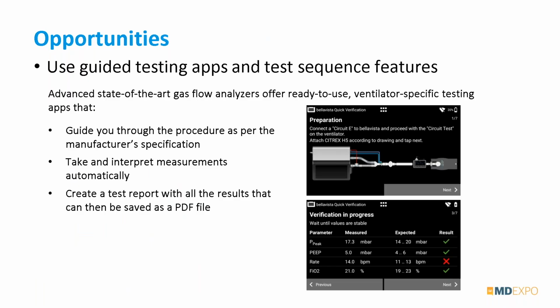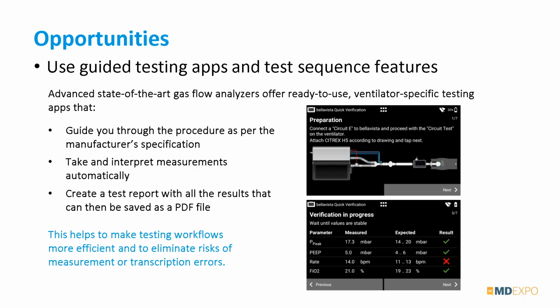So there are gas flow analyzers out there that have these sequences running on the device or on a separate software that can really help you overcome all the challenges we discussed so far, because they make the calculations for you and make sure that you follow the sequence correctly. And they also make sure that all the settings are correct because they are designed for a specific ventilator. So it already makes all the settings for gas type, gas standard, trigger settings, and everything in the background for you. So this can be very helpful then. And of course, this also helps to improve your productivity because you don't have to do all the calculations yourself because it's done automatically.